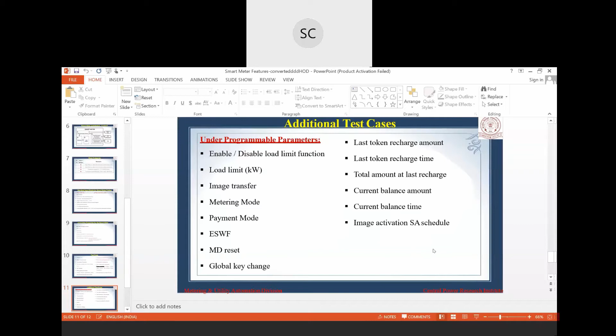Import means we are drawing power from the utility. In export mode, we are pumping power from the consumer premises to the grid. So this mode we can set. This is possible through the event called metering mode. Payment mode. Again, as in the case of mobile, as all of us know, it is prepayment or post-payment. All the payment modes are possible in smart meters also. Again, MD reset, ESWF, that is okay. Global key change. It is not the correct time to explain this. These are common features like last token recharge, when it was last recharged, total amount of last recharge, and all this. These are the general parameters used.